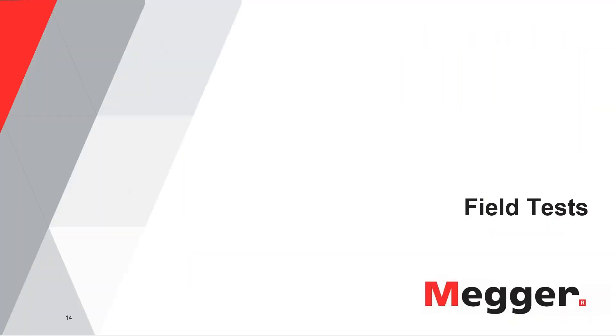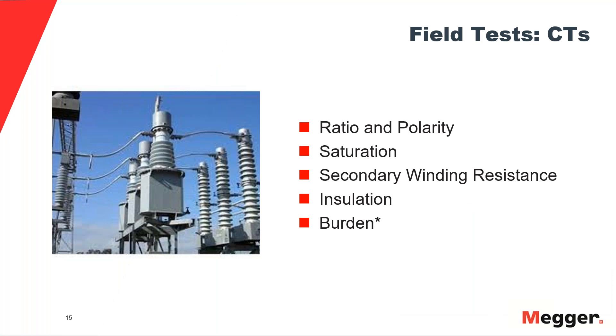Hence the need for testing, the need for maintenance, and predictive testing for these type of devices. So what can we do in the field? For CTs, the tests we can perform are: ratio and polarity, saturation measurement, secondary winding resistance, insulation, and the burden — with some special considerations we are going to discuss.